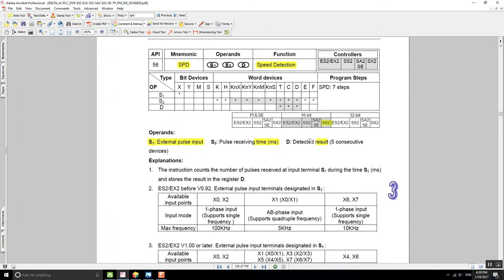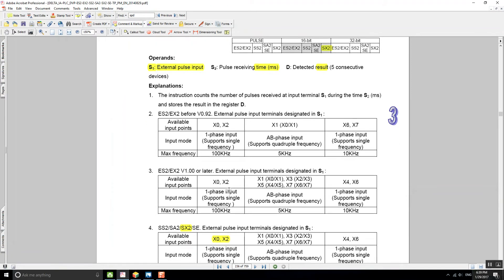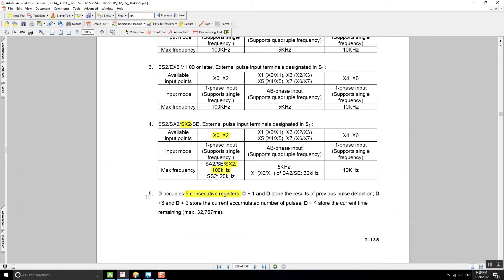The result is going to be stored on the D device. There's a note that says five consecutive devices will be used by the PLC. Note 5 tells you what each device is used for: D and D+1 store the result of the previous pulse detection, and D+2 and D+3 store the current accumulated number of pulses.